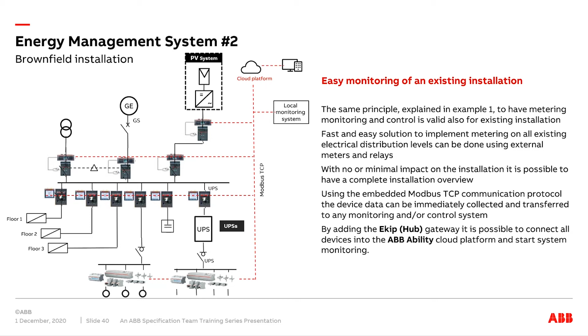So when we look at the design here, we've still got circuit breakers in there, but we're adding intelligence such as metering, as you can see on the left-hand side. We can also add other control mechanisms at the circuit breaker level, and at final distribution we can add intelligence through sensor-based technologies. We'd connect that back in a very similar way as the previous example, through a Modbus network, and look at the data locally and again on a cloud-based platform, utilizing devices such as our Ekip Hub and the ABB Ability Cloud platform, allowing you to interrogate the data on an existing installation.